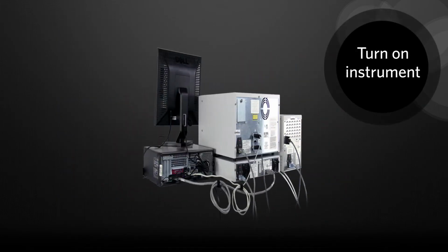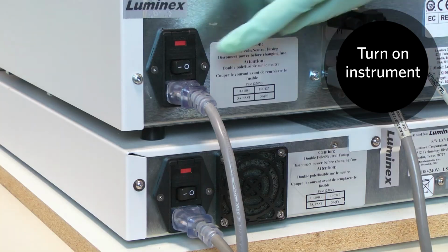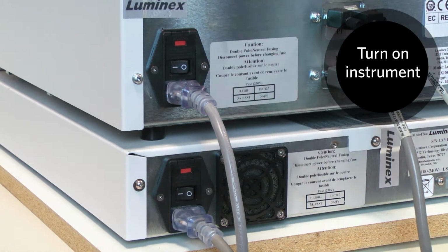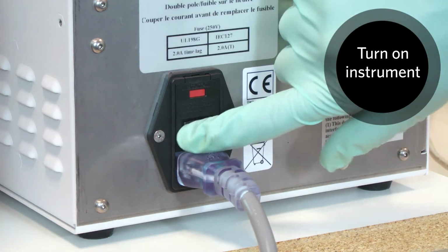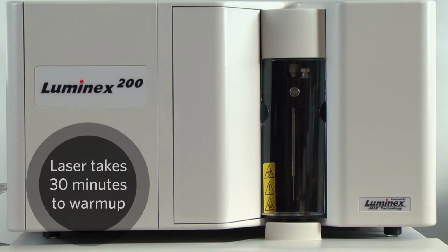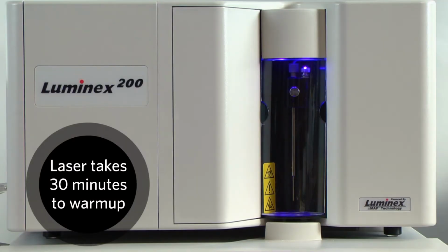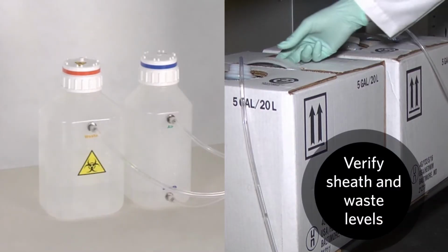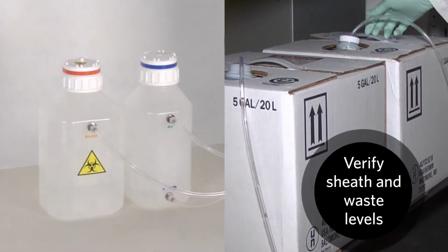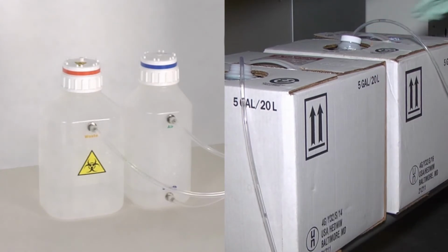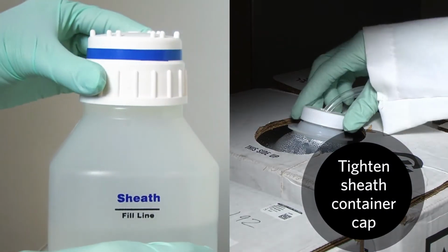Here's how to start up the Luminex 200 instrument. Turn on the Luminex 200 analyzer, XY platform, and, if used, the Luminex Sheath Delivery System. The laser takes 30 minutes to warm up. Verify the levels of sheath and waste fluid. Tighten the sheath container cap.